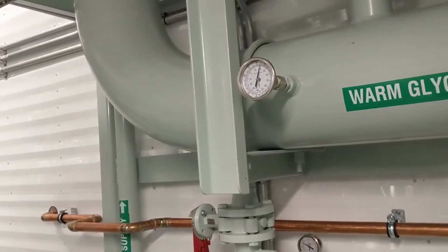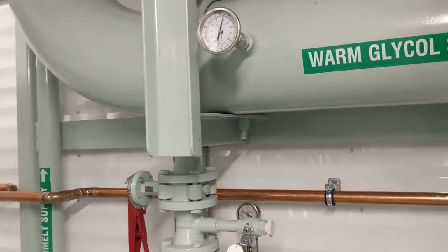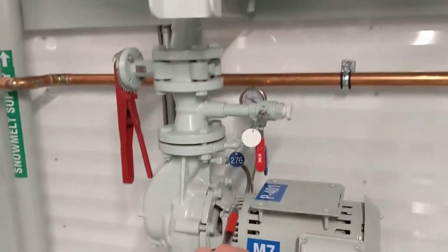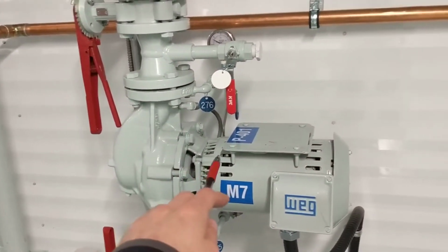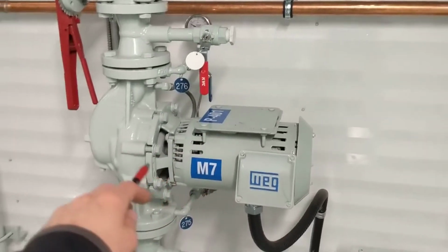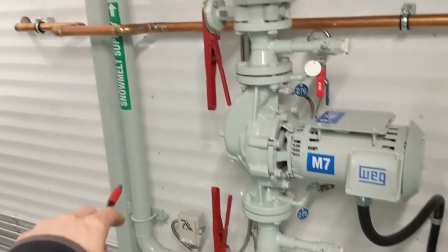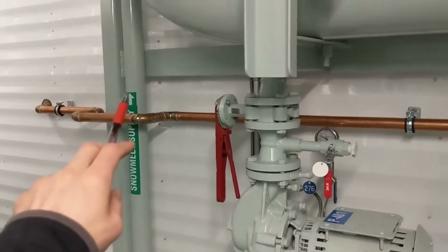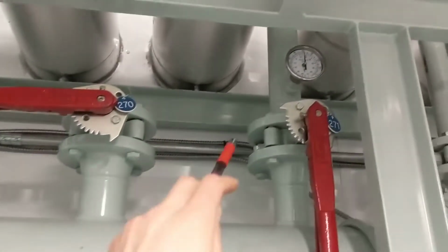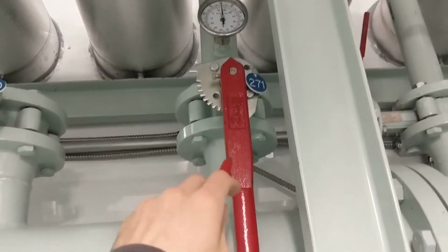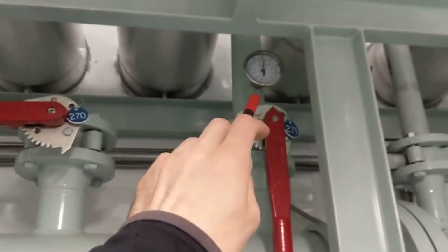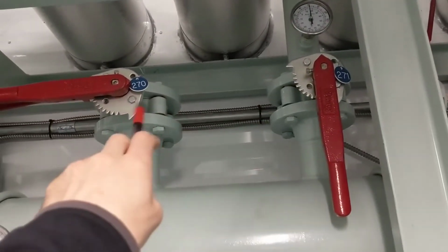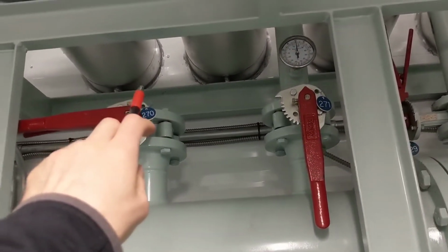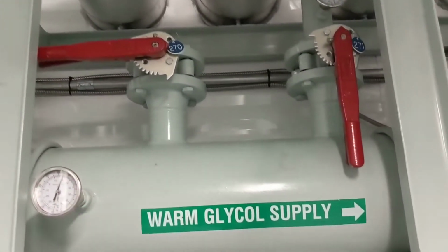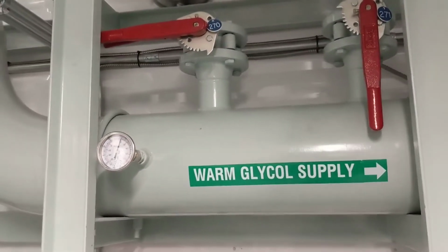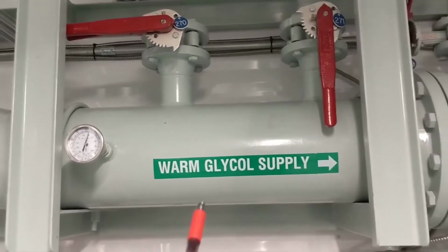So the other thing that the glycol is doing is it's circulating through the snowmelt pit. So this pump here, P401, circulates the warm glycol out to the snowmelt pit, and it returns back here when it's coming back from the snowmelt pit. This is capped off because that's been designed in case we ever have another use for the warm glycol.